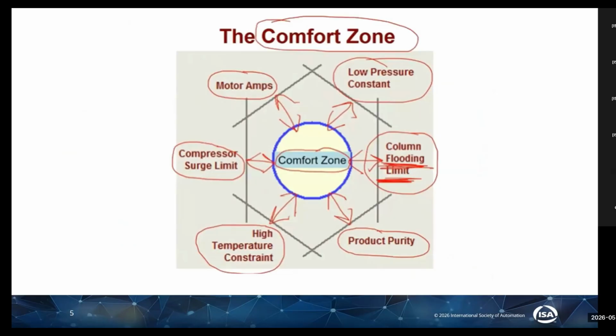Okay, so why do we need PID controllers? If you can see in this diagram, this is the comfort zone. Normally, without a PID controller or with a bad PID controller, we are operating the plant far away from the optimum set point. For example, I have a compressor, and this is a refrigerant compressor. To refrigerate and to condense more product, I have to increase the speed.